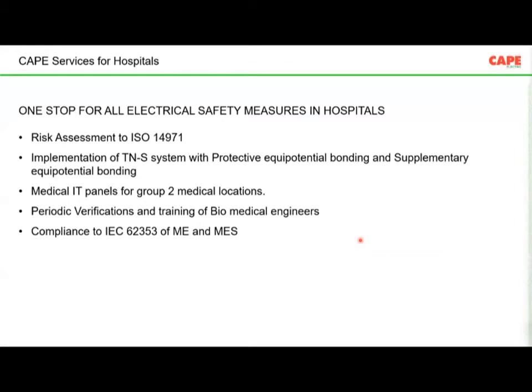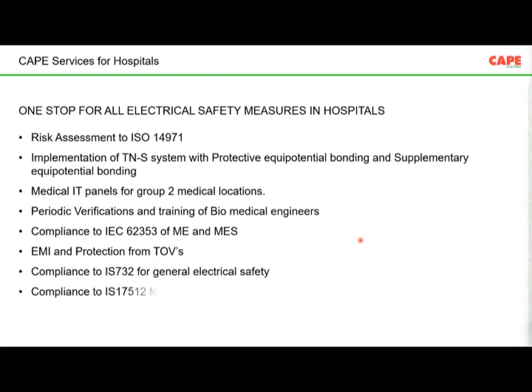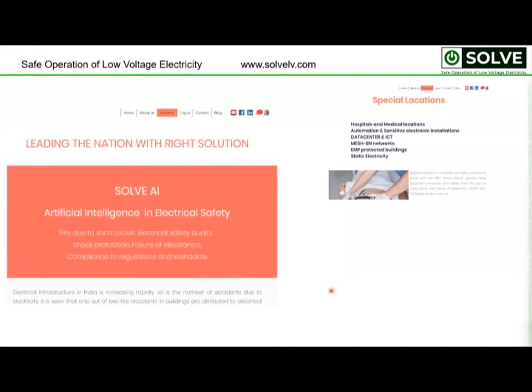Compliance to IEC 62353 for medical equipment and medical equipment systems. Then EMI and protection against temporary overvoltages. As you know, most of the time electronic equipment fails due to small issues. If those small EMI issues are handled well, the life of the equipment will go very high, and without any accident you can enhance the life of the equipment. And compliance to the standards IS 732 and IS 17512 can be made. So these are the safety measures which we are offering.